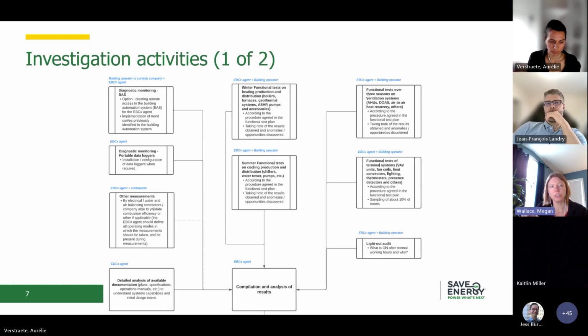This slide shows a flow chart of the investigation activities. So the EBCX agent will come in and do diagnostic monitoring. If there's a control system in the building, a BAS, a building automation system, the EBCX agent will look at reviewing and implementing trend logs, and as an option, if it's possible, set up remote access to the BAS system so that they can review how the building is operating live.